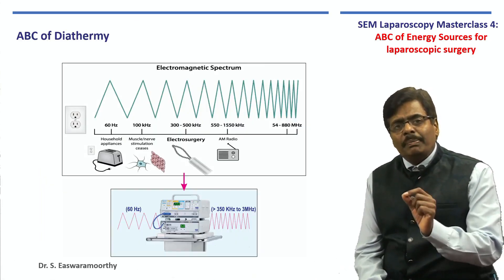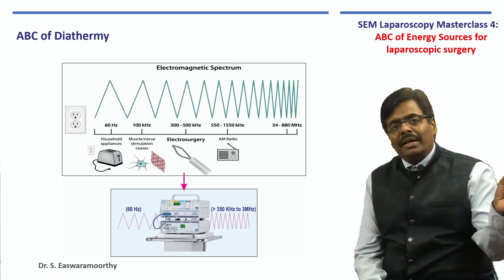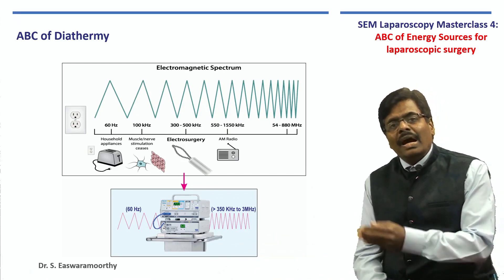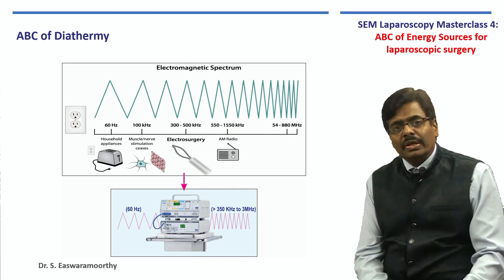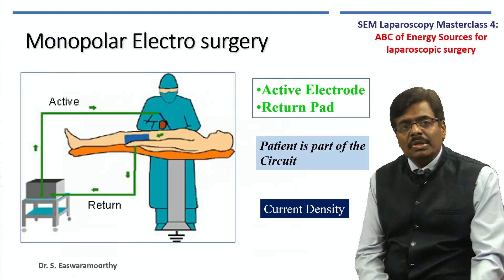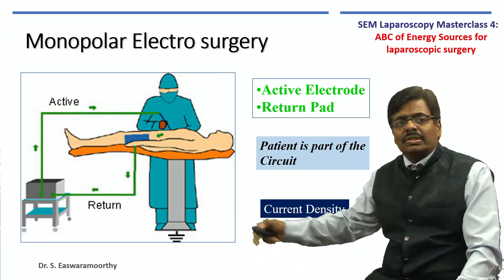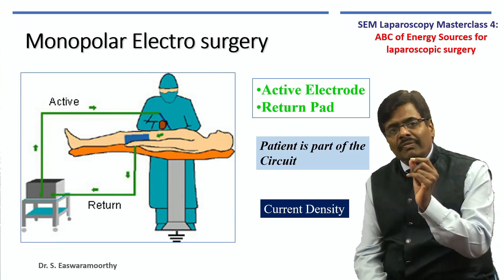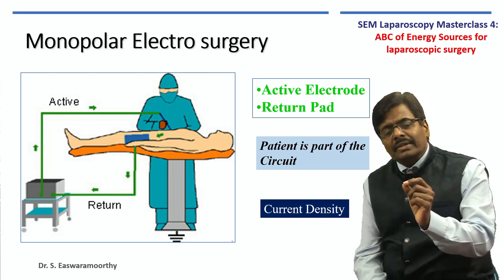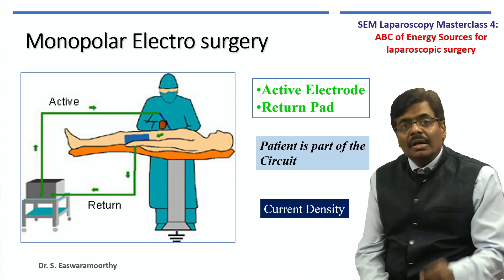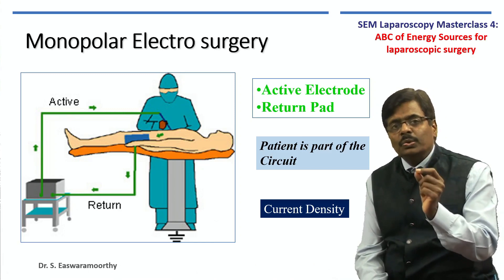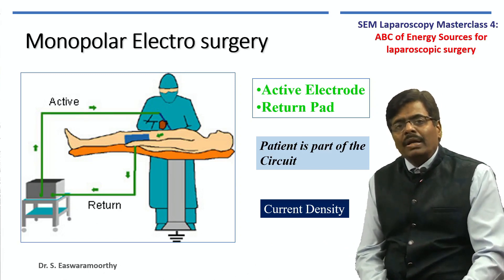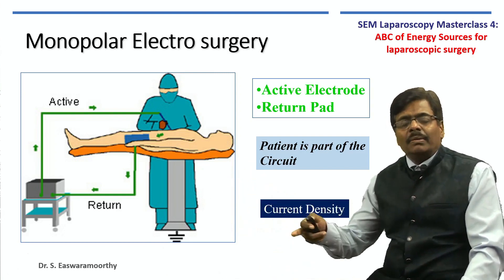When we plug in the diathermy machine to our electrical supply, the low-frequency household alternating current is converted into a very high-frequency current — that is all the machine is doing at its core, but a good diathermy machine will do a lot more. The electrons coming from the machine, once activated, go through the active electrode and cause the desired effect wherever you apply it. After that, the electrons travel through the patient — the patient is part of the circuit in monopolar electrosurgery — travelling through the path of least resistance.